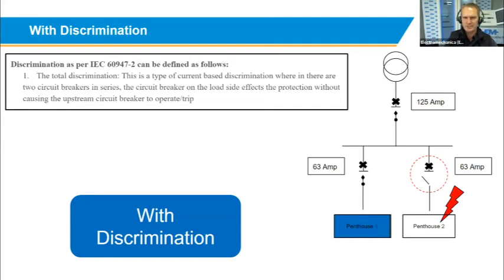There are a few different ways of doing discrimination. You can do discrimination by curve: B, C, and D curves, slow and fast tripping curves. In this application, I've used normal current discrimination, where you use different current ratings upstream and then downstream. And in moulded case circuit breakers, you also have the functionality of setting the electronic side of it, the time delay. So you can play around with the time delay on moulded case circuit breakers to get the discrimination effect that you would like.